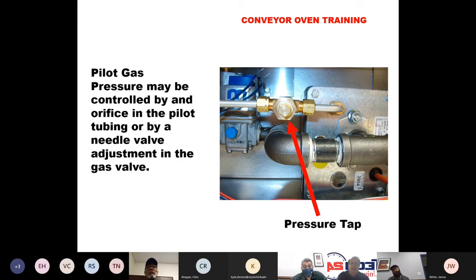This pressure is controlled by an orifice in the pilot tube, or there may be a needle valve that you adjust on the gas valve itself. When we get in the middle, I'll show you how that adjustment works.